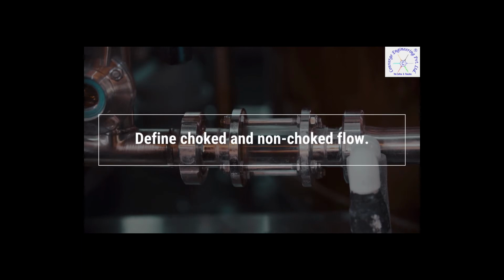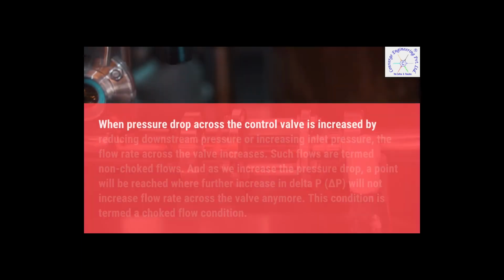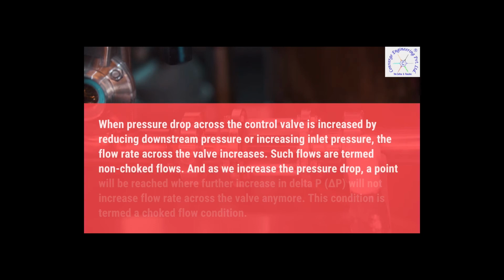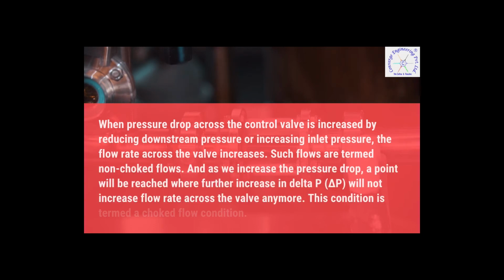Define choked and non-choked flow. When pressure drop across the control valve is increased by reducing downstream pressure or increasing inlet pressure, the flow rate across the valve increases. Such flows are termed non-choked flows. And as we increase the pressure drop, a point will be reached where further increase in delta P will not increase flow rate across the valve anymore. This condition is termed a choked flow condition.